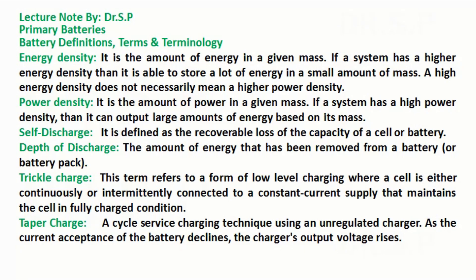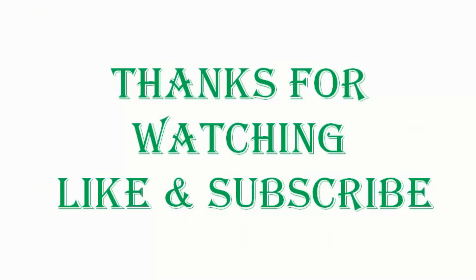Trickle charge: this term refers to a form of low-level charging where a cell is either continuously or intermittently connected to a constant current supply that maintains the cell in a fully charged condition. Taper charge: a cycle service charging technique using an unregulated charger, where as the current acceptance of the battery declines, the charger's output voltage rises.